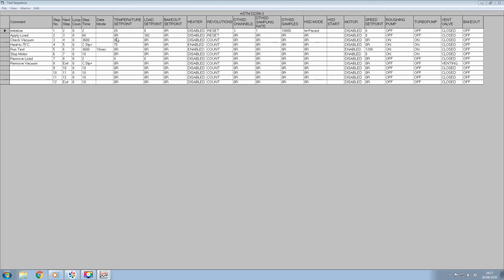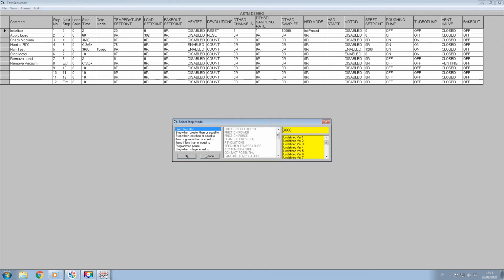In the third step, both the roughing pump and the turbomolecular pump are enabled. The step time is set to 3,600 seconds. As well as programming a fixed time, the step time can also be programmed as a conditional step using the associated parameter box. There are a number of conditions that can be selected. Right-click on the step time box. In this case, I'm choosing step when less than or equal to.